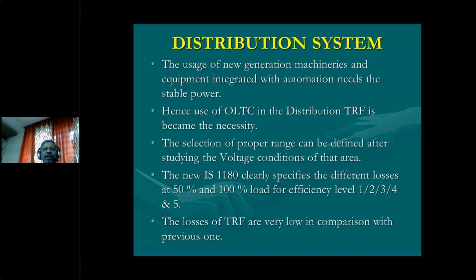The new standard is IS 1180, which clearly specifies the different losses at 50% and 100% load for the efficiency levels from 1 to 5. When we talk about the new IS 1180, what was the previous IS? It was IS 2026. It still exists for any non-standard transformer which is not covered in 1180. In that previous IS, the losses were mentioned as being mutually acceptable to the user and the supplier.